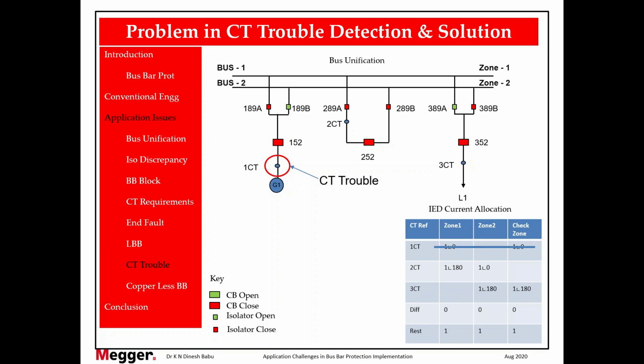This will result in elimination of the current in the main zone as well as the check zone, because both the zones are using the same CT core. In such a situation, how will the relay provide the security we need? The conventional method is actually to block the bus bar using CT trouble. This is not the right way to do it. With the availability of sophisticated algorithms in numerical relay, CT trouble should not be used to block the bus bar.